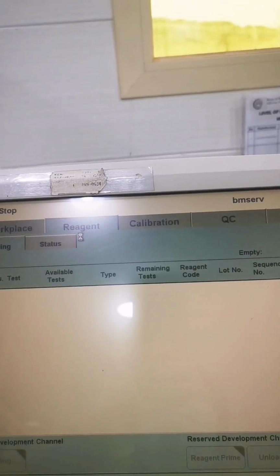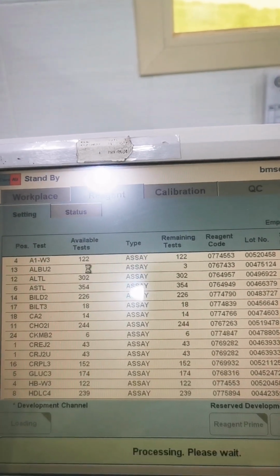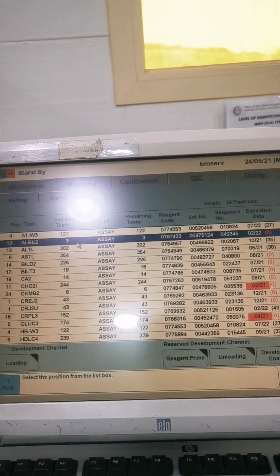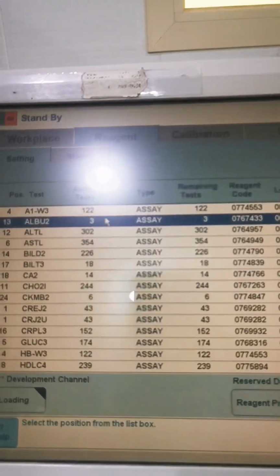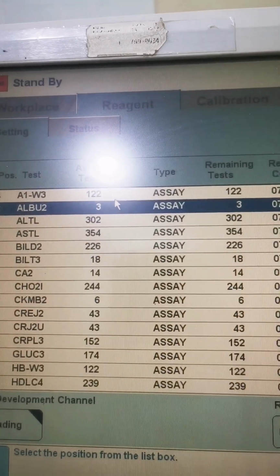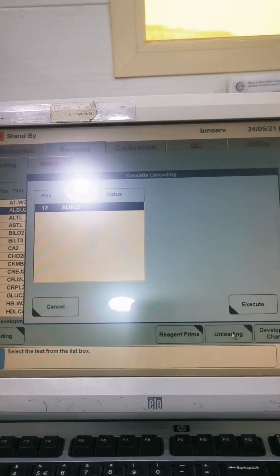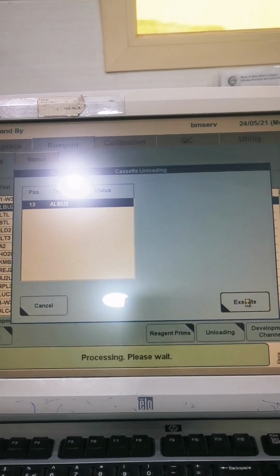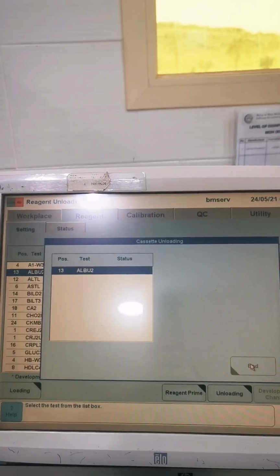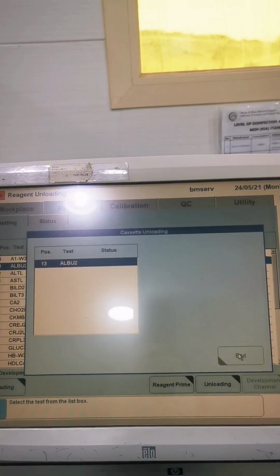The first thing to do is to go to the reagent. Let's check the available test for each analyte. So position number 13, which is the ALBU2, remaining test will be 3. Click ALBU2, or the analyte that you need to change, then click unloading. Once you click unloading, click execute. Now the machine will start to process to remove the ALBU2 reagent.